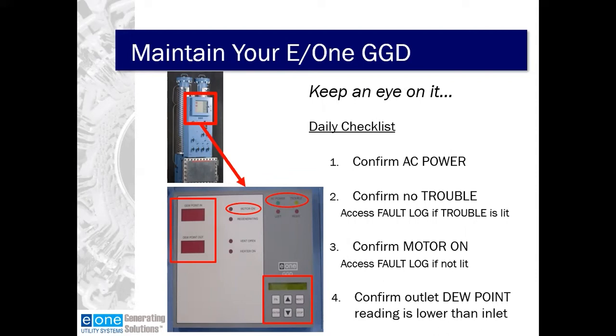So now that we've gotten to know our gas dryer, it's important to keep it running and important to maintain it. The first thing is to keep an eye on it. Like any other piece of equipment you have operating in your plant, there are some daily checklists that we need to perform on the equipment. We'll walk through that here for the gas dryer. So again, we're referring here to that generator gas dryer display, which is behind the display door. The first thing we want to do on the daily checklist is confirm that the AC power is on, so that the LED is active.